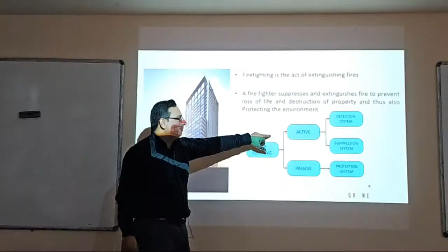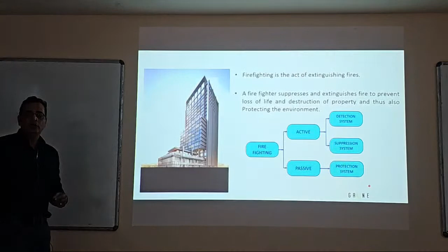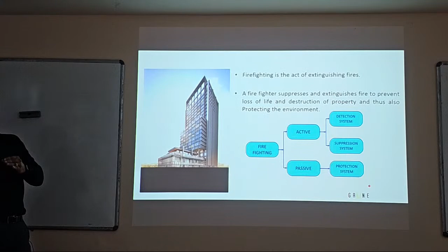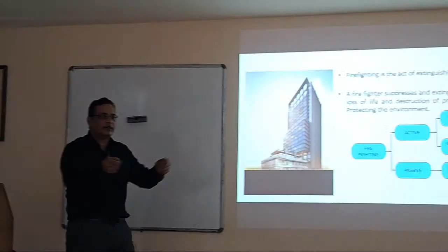Active is coming to know which building, which room, what floor - that particularly in an auditorium there has been an incident. Then the reaction is directly towards that auditorium rather than spreading across the entire set of buildings to find out where the issue is. That helps by the detection system. And then suppression is basically designing for sprinklers or extinguishers - that's just suppression. So that's how you define your firefighting considerations.